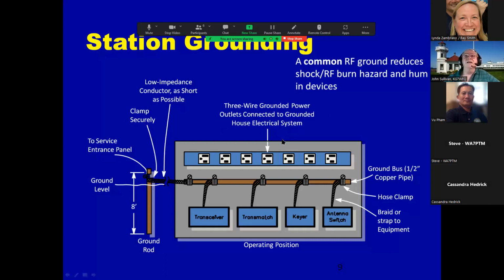Here's an example. They've got a heavy copper pipe they're using as a ground bus. Each piece of equipment is connected to that bus with copper braid or strap, and that bus is in turn connected to a ground rod in the ground. It should normally be 8 feet long, which is really long when you think about it, and it's often difficult to drive into whatever the soil type might be in your area.